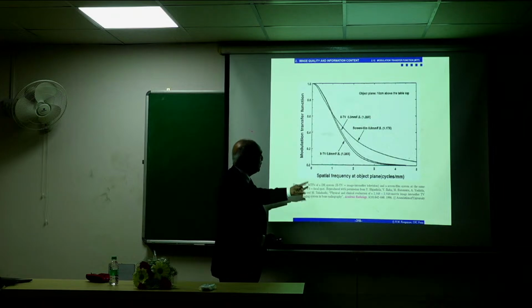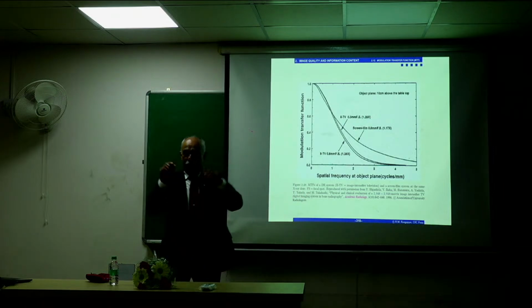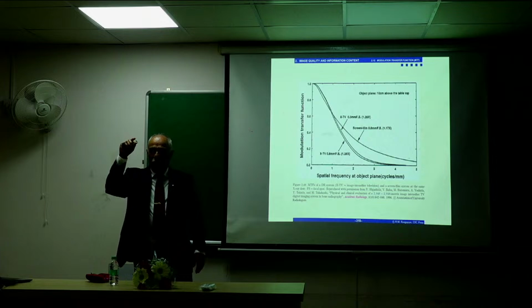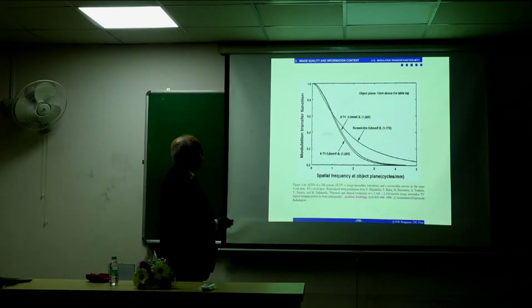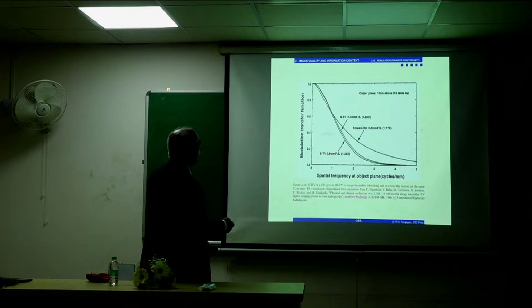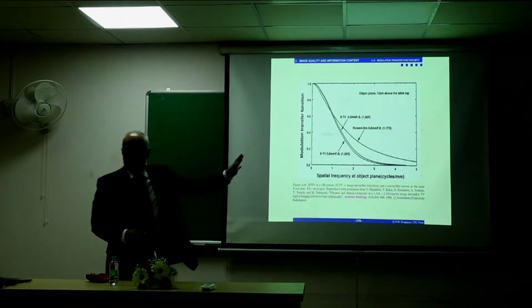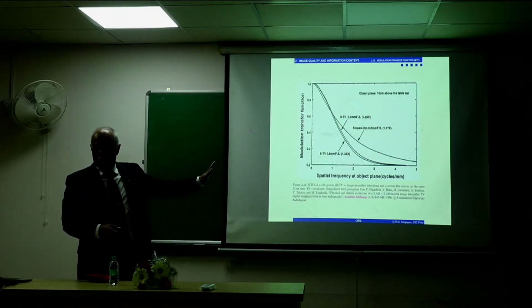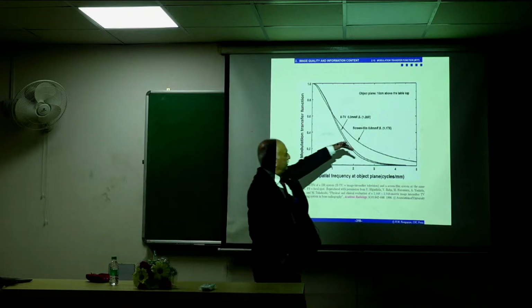And FS is focal spot. I mentioned earlier, if the focal spot in the X-ray tube is too large, there is blurring. So they are comparing here. This is image intensifier TV with 0.8 millimeter focal spot and with 0.3 millimeter focal spot, and this is screen film. Obviously, screen film was at that time better than the digital. More area under the curve.